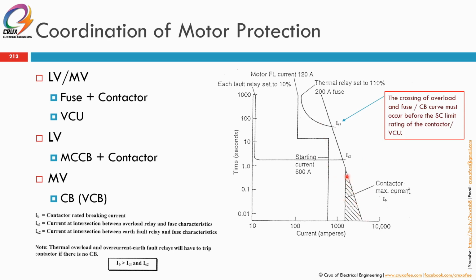So in this case, 10 times 200 amps is around 2kA lah, or 2000 amp. So this is 1000 amp, 2000 amp lah. So we cannot allow the contactor to break for faults more than 2000 amp. So that's why we need to make sure that the fuse breaks in before reaching 2000 amp. So in this case, close to 1000 lah. So if there's any fault above 1000 amps and above, so the overload is here, but the fuse is below the overload curve, and the fuse will be blown first instead of the contactor being open. If not, the contactor life will be reduced lah, because it's breaking the current beyond the capacity of its short circuit rating. So this is one particular. If you are using this with MCCB, you must make sure that the high set instantaneous of the MCCB comes to this point. Must come in before the contactor maximum short circuit rating.